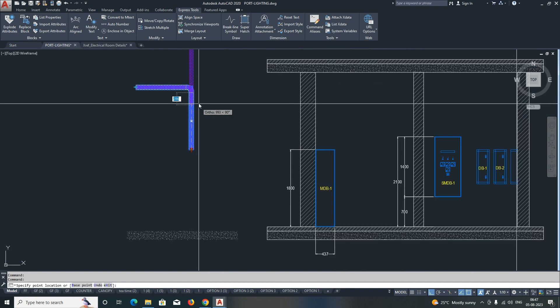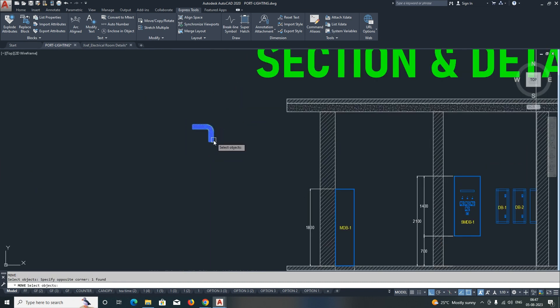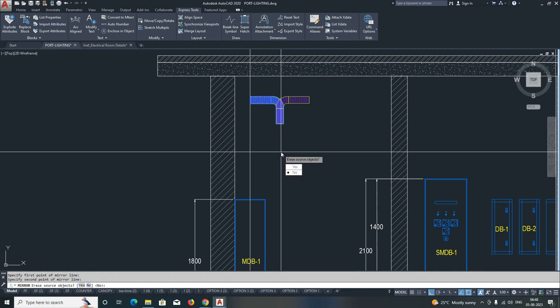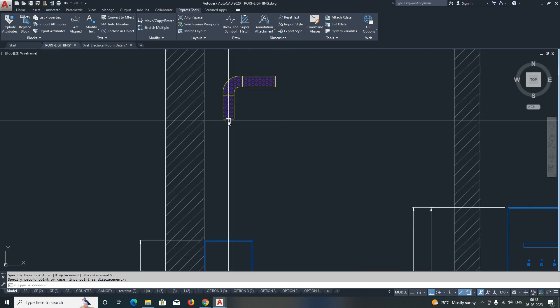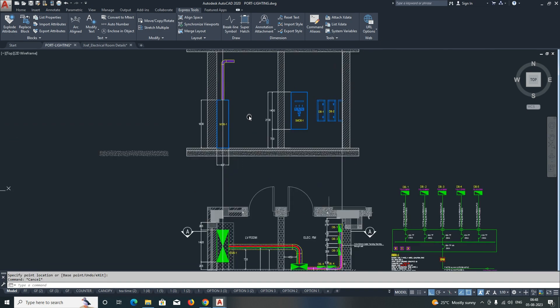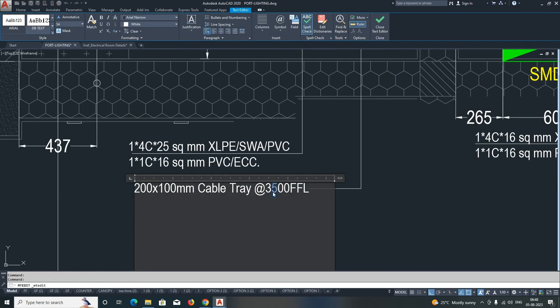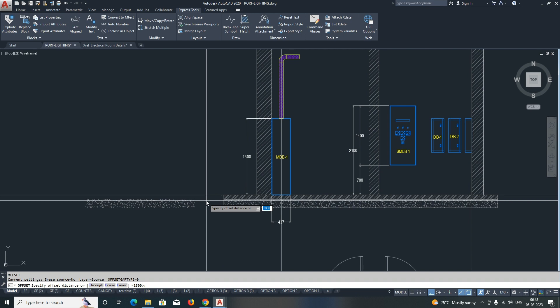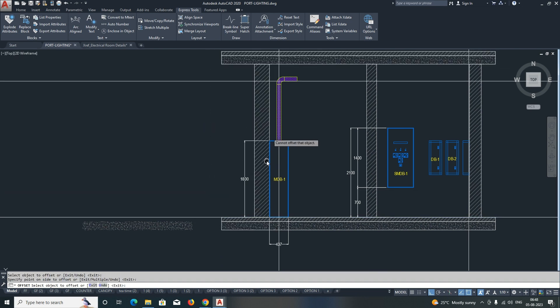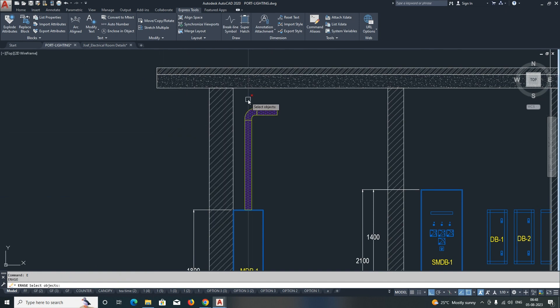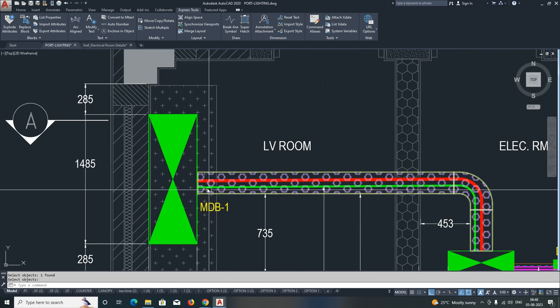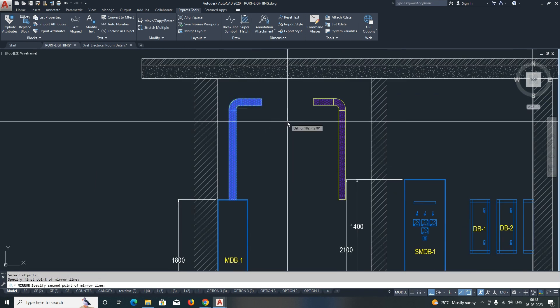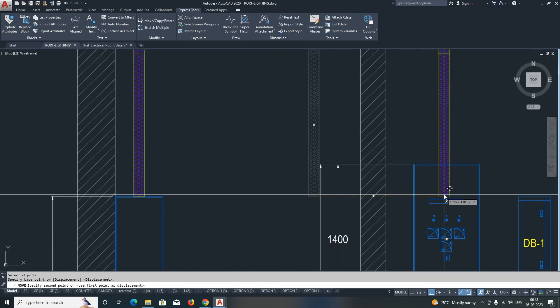We need to connect the cable tray to all the panels. I'm picking this cable tray coming up to the center of the panel and mirroring it to connect here. The level — for example this one is going to 3500, I'm changing it to 3200. Take an xline from here, offset it, and give 3200. So the cable tray is running at 3200 and connecting to the sub-DB.